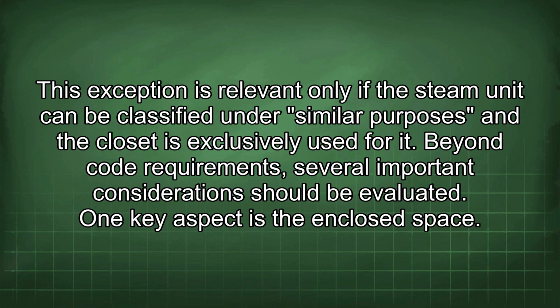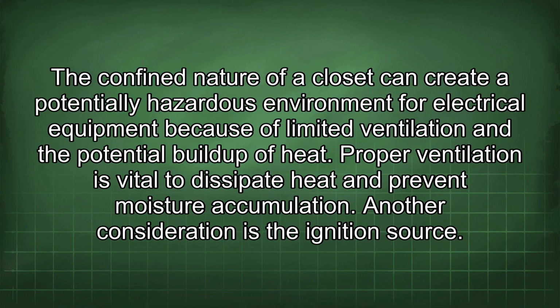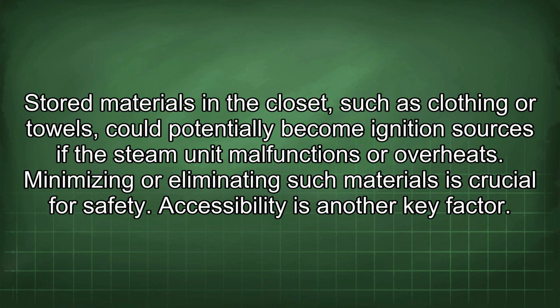One key aspect is the enclosed space. The confined nature of a closet can create a potentially hazardous environment for electrical equipment because of limited ventilation and the potential buildup of heat. Proper ventilation is vital to dissipate heat and prevent moisture accumulation. Another consideration is the ignition source. Stored materials in the closet, such as clothing or towels, could potentially become ignition sources if the steam unit malfunctions or overheats. Minimizing or eliminating such materials is crucial for safety.